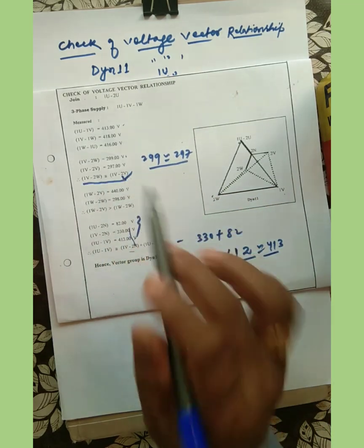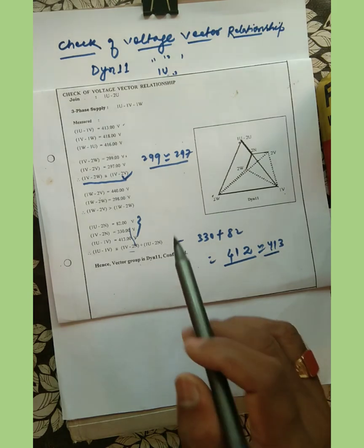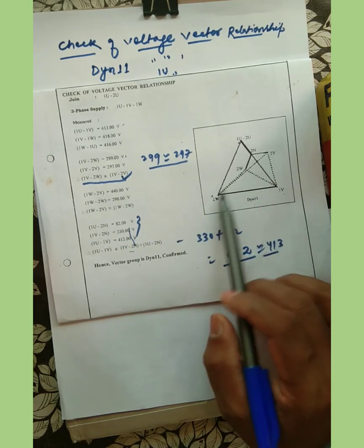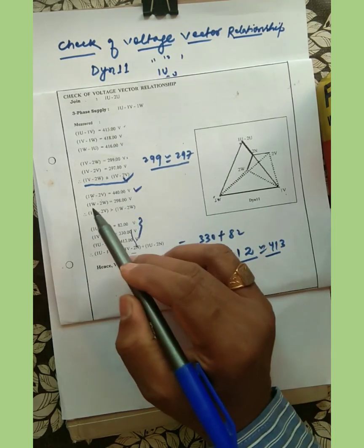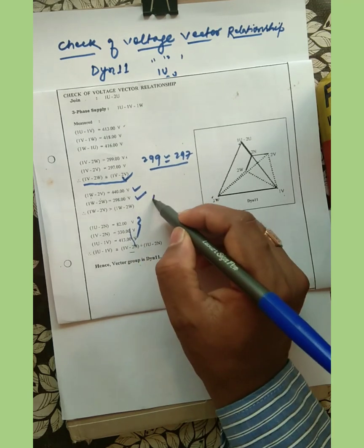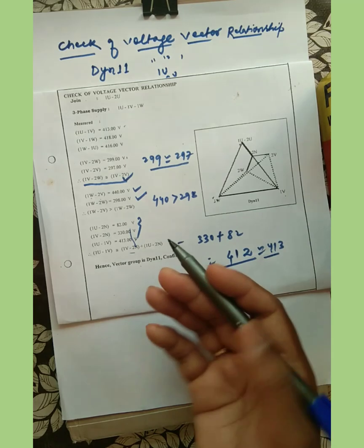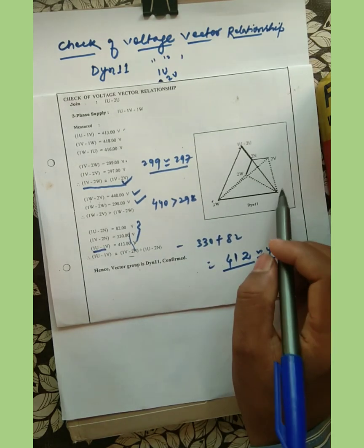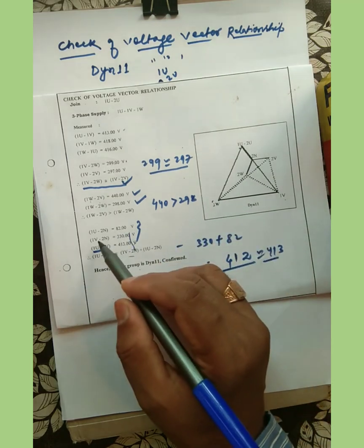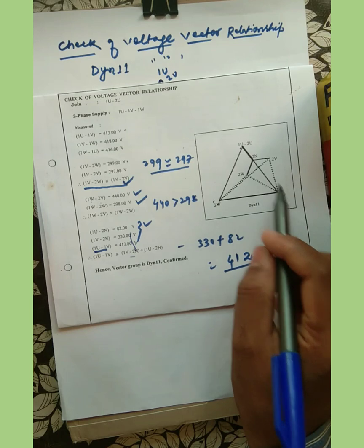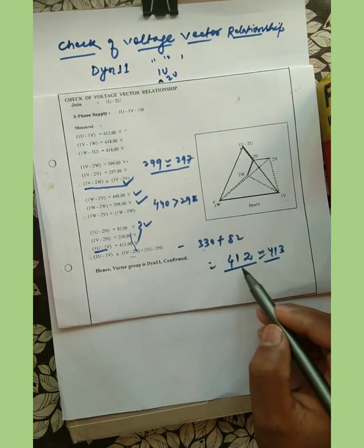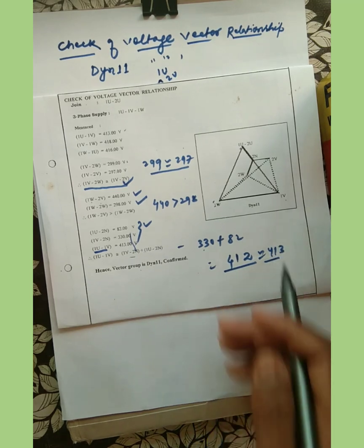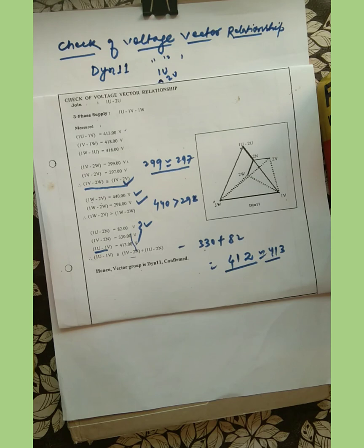For the second relation, 1W-2V should be greater than 1W-2W. They measured 1W-2V as 440V and 1W-2W as 298V, so 440 is greater than 298 — hence it is proved for DYN11. For the third relation, 1U-2N is 82V and 1V-2N is 330V. Adding them: 330 plus 82 equals 412, which is almost equal to the measured 1U-1V of 413V. We have proved all three equations and can confirm the vector group is DYN11.